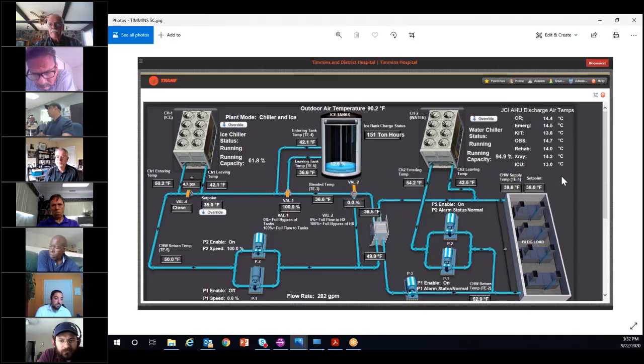And also, we've minimized the amount of equipment involved. They had 4 chillers before that were all operating on water. For us on the call here, we'll need to drain down and winterize those chillers. So rather than having to winterize and fill 4 chillers each year, now they're just doing it to 1 chiller, and the 1 glycol chiller can essentially stay charged all year with 50% glycol in there, which is well protected for the Sudbury winters. And of course, rather than having a service maintenance agreement on 4 chillers, they're only looking at 2.